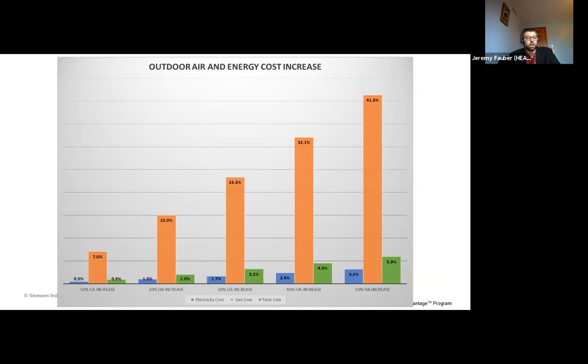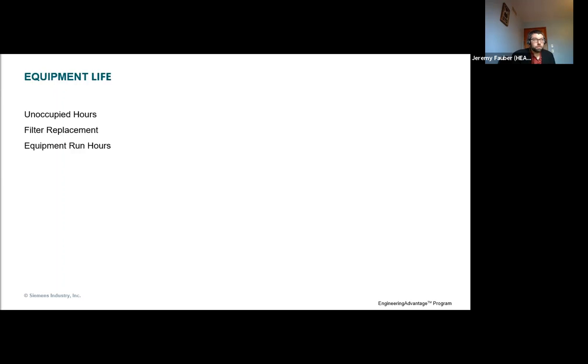So for our next slide, we want to talk about how the equipment life is going to be impacted by this. One item I want to talk about is unoccupied hours, which Matt didn't go into. One of the suggestions out there by CDC and ASHRAE is to deliver outdoor air and recirculated air during either post-occupancy or pre-occupancy. The idea is to flush out the air. If you think about it, someone's in there breathing, talking, bioaerosols going in the air, and it takes a certain amount of time of air recirculation to get that out. So when you've got a building that's only going to be occupied, say 13 hours throughout the day, either after people have left, keep running the HVAC system and clean out that air, so when people come in the next morning it's clean, or you can do that just before people come in.